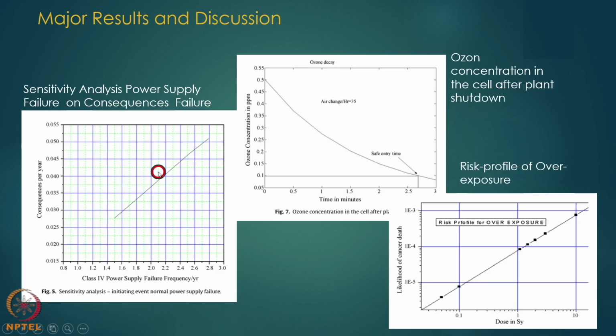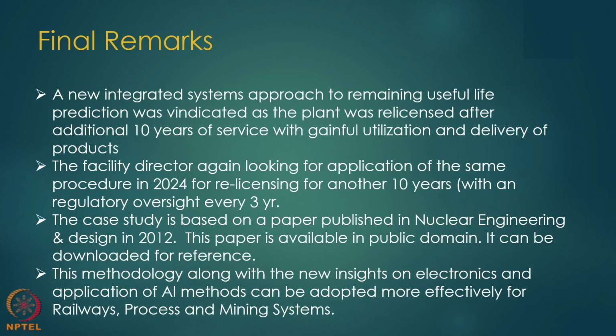That was seen and mapped, and finally the risk profile results show that compared to what is permitted for irradiators, dose consumption was minimal or nil. This was for ozone: if it forms in the cell, what is the impact? A safe entry time was identified, around 2.5 minutes, or less than 3, and these parameters were developed. With these results the regulator agreed that this plant can go for life extension for 10 years.